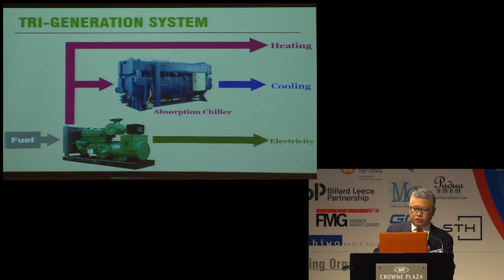Trigeneration is most suitable for hospital application because there is a steady requirement for electricity, cooling, and heating. In a trigeneration system, waste heat is recovered from the power generating equipment to provide water heating, and an absorption chiller driven by the waste heat provides chilled water for air conditioning. Although the system is quite common overseas, it is not actually used in Hong Kong because of our low electricity tariff. But recently a pilot scheme has been implemented locally in a hospital in Tai Po, using the methane gas recovered from an adjacent landfill site as fuel to produce electricity, domestic hot water, and chilled water for air conditioning.